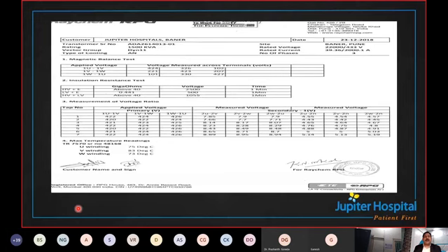Now, if you see here in a dry type transformer, there is a degree that has been shown here. So you need to check every time all these windings, whether that is properly happening or not, because that has to be done by a third party. We cannot say that we are going to do it ourselves. It's not practically possible.